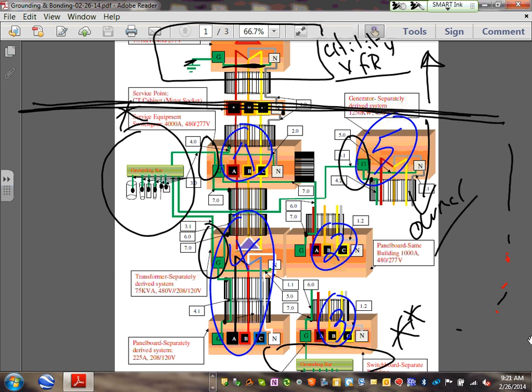You can see the service point is so important when it comes to the power system. And the service point is typically done right at the service CT cabinet or termination box. They bring their cable from one end, we bring our cable from the other end, and this is where we meet each other. This side is yours, this side is mine, in terms of conduit, wire, grounding or ungrounding. Any comments, gentlemen? Any questions? Matt?